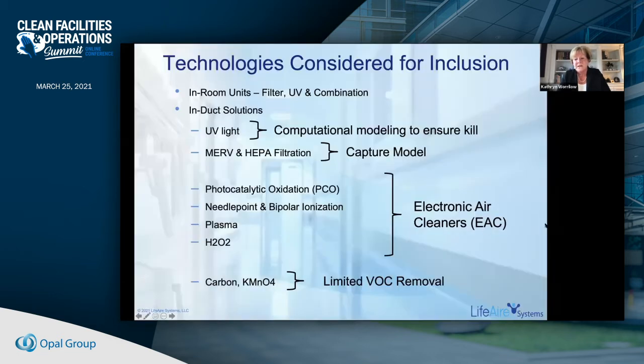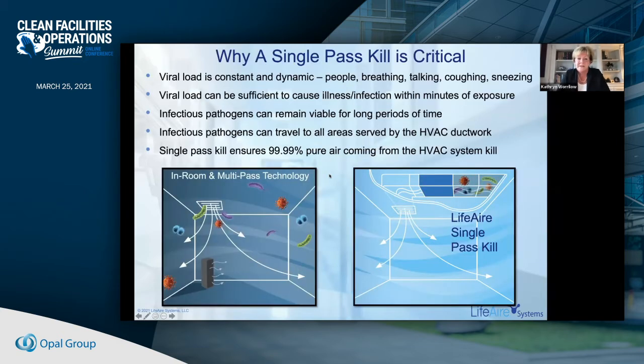We also looked at a lot of electronic air cleaner technologies - PCO, needlepoint, bipolar ionization, plasma, hydrogen peroxide - and chose to stay away from these as well, because a lot of them require catalysts, and catalysts degrade over time. Therefore, the effectiveness of your technology can degrade over time. A lot of these can also produce toxic byproducts or intermediate molecules, free radicals. Some produce VOCs. Our goal was to remove the variable of air, not contribute any other byproducts by virtue of the technology. And finally, carbon and potassium permanganate, the go-tos for VOC removal - these do work well, but only on certain biochemical families of VOCs. So for a variety of reasons, we decided not to focus on the pre-existing technologies.